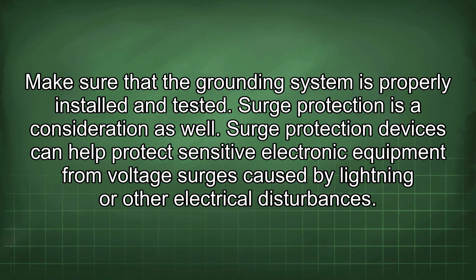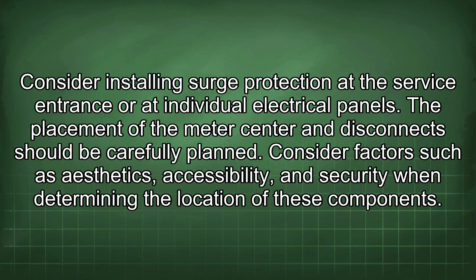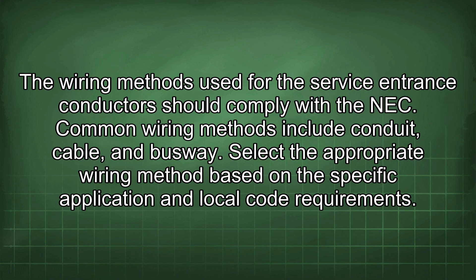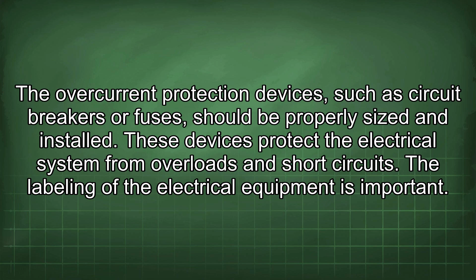The placement of the meter center and disconnect should be carefully planned. Consider factors such as aesthetics, accessibility, and security when determining the location of these components. The wiring methods used for the service entrance conductors should comply with the NEC. Common wiring methods include conduit, cable, and busway. Select the appropriate wiring method based on the specific application and local code requirements. The overcurrent protection devices, such as circuit breakers or fuses, should be properly sized and installed. These devices protect the electrical system from overloads and short circuits.